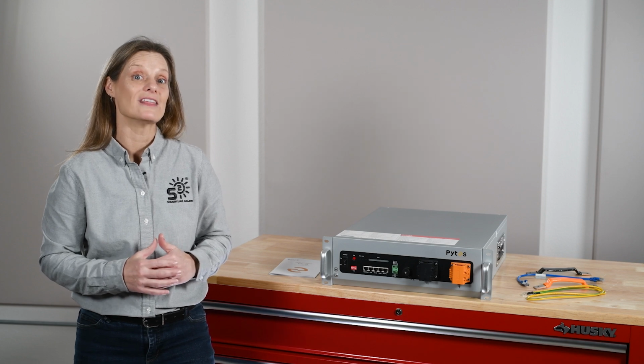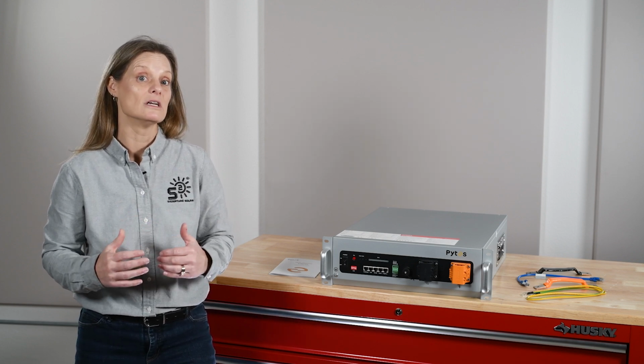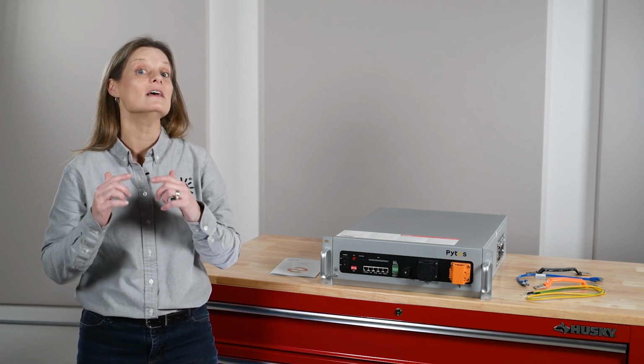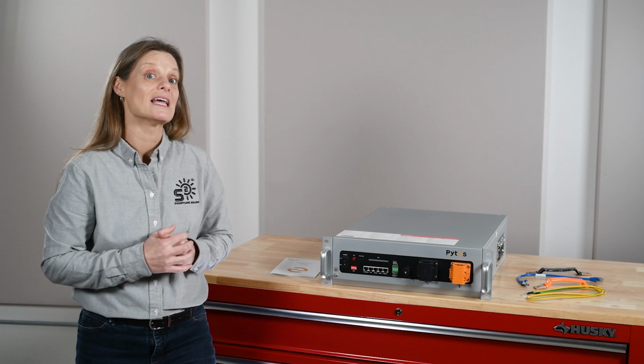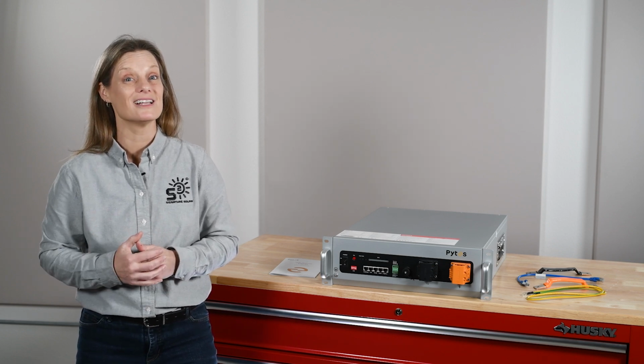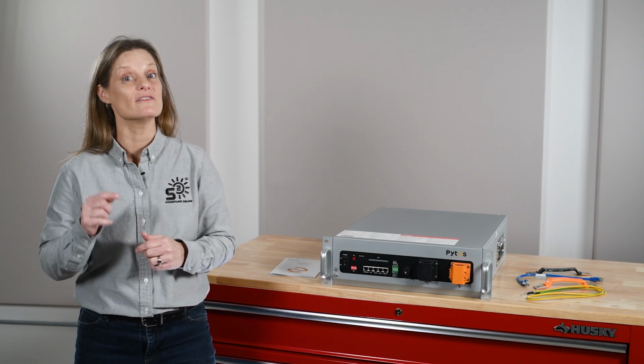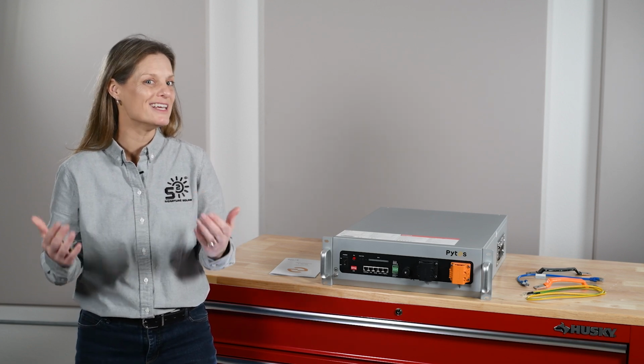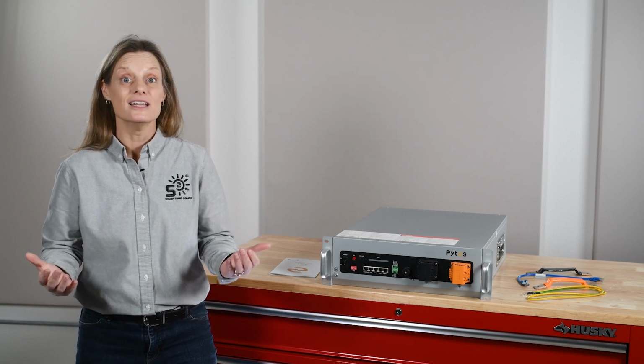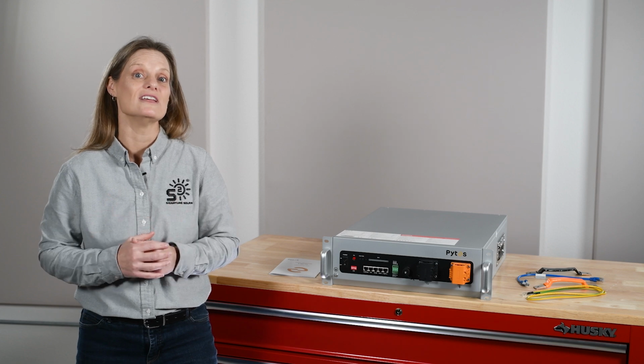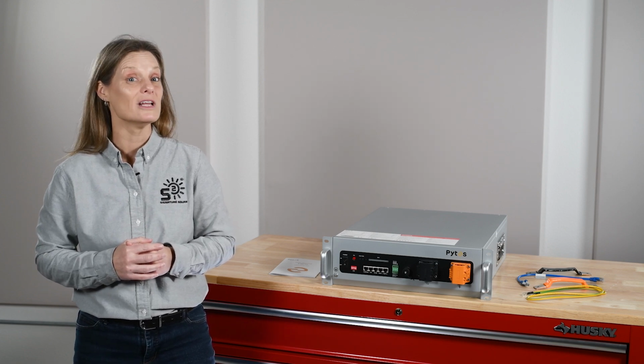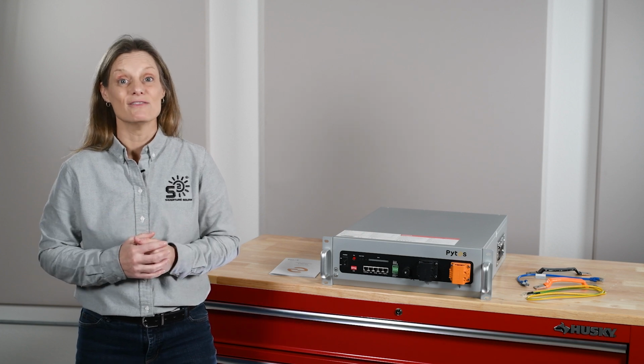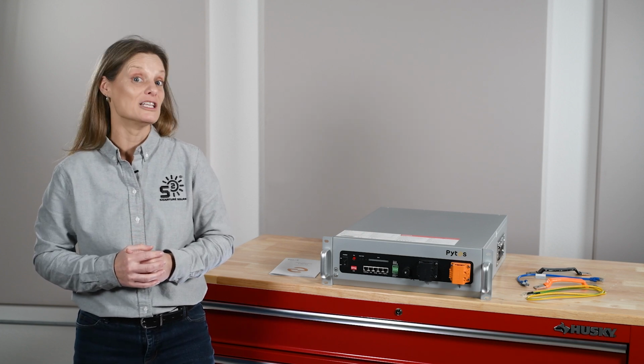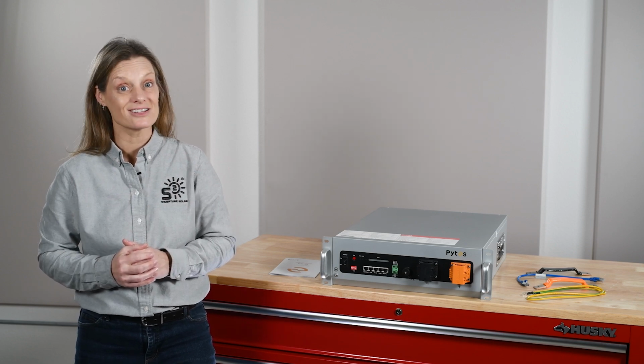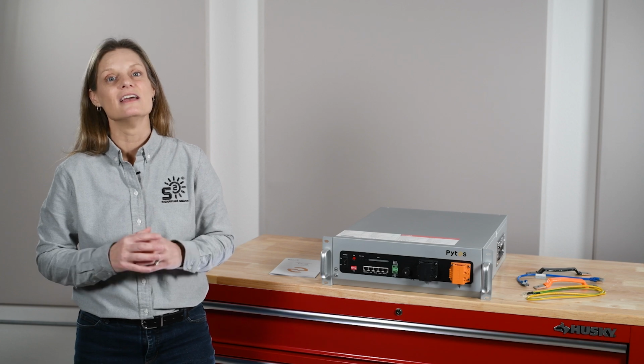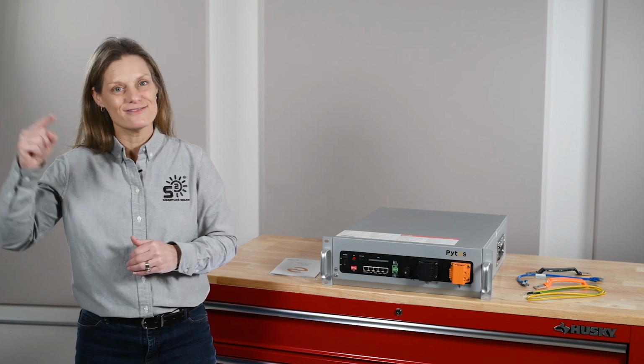Pytes has also equipped the V5 with a self-designed battery management system, which includes multiple layers of protection to ensure safety and long-term reliability. Each battery undergoes a 48-hour aging test before leaving the production line, resulting in a remarkably low failure rate of under 0.3%, with most issues easily resolved in the field if they arise. In addition to its build quality, the V5 meets important safety and quality standards, including UL 9540, UL 9540A, UL 1973, and CE certifications. It's backed by a 10-year warranty, providing over 6,000 cycles at 90% depth of discharge and a round-trip efficiency of over 95%.